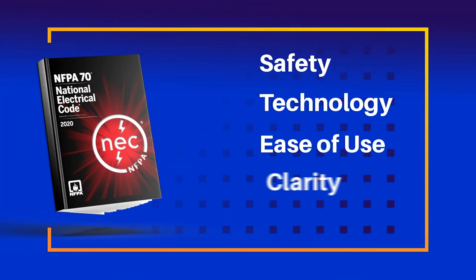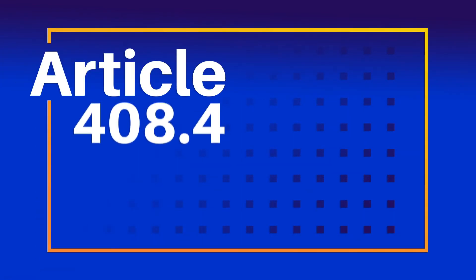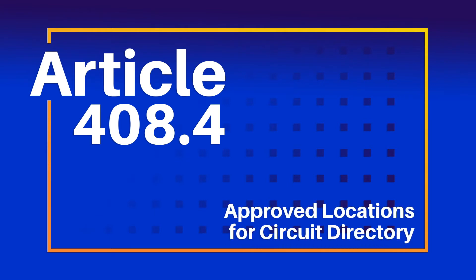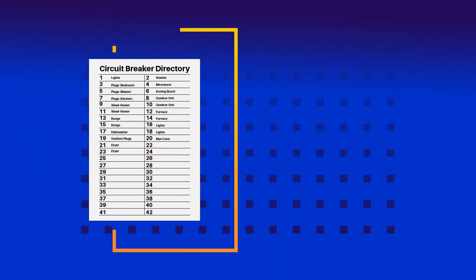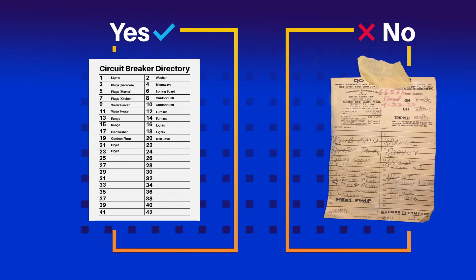Code changes happen for many different reasons, and sometimes it's hard to figure out what the intent of the change is. It might seem subtle when looking at the change made to 408.4 — approved locations for circuit directory for a panel board. But having an accurate and legible circuit directory for a panel board can not only save time, it also seriously improves safety.